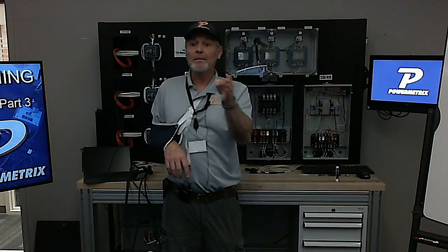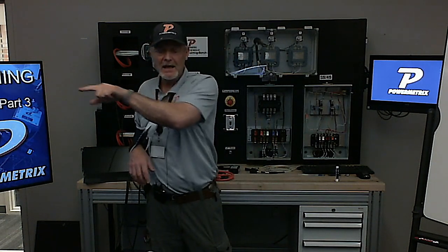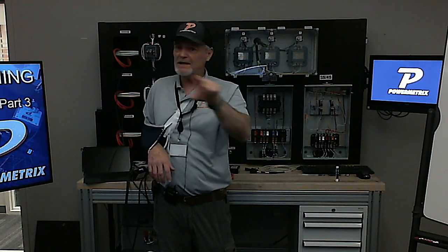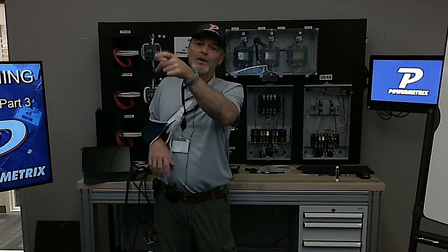So I do have a connect view. If you look at connect view on the equipment, it shows B phase being connected. If you go to meter view, it shows VAB, and you don't see any yellow, just blue and red vectors, but it's showing you VAB. Like I said, if you see more than one letter off of that, it's referencing. So in this case, you can look at Connect View to make sure and see where you actually make your connections at the test switch.